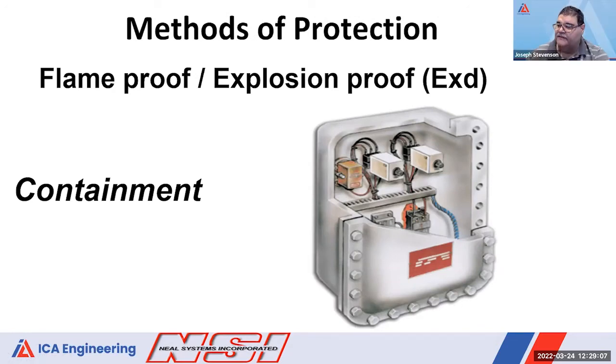Right. That's the thing, it's definitely a maintenance issue, because if you do have to access these locations, there's a lot of hoops you have to jump through, whether it be a chemical sniffer or shutting down power to the area. So a number of precautions you have to take, and people very often will cut corners, because it takes a lot of time to unbolt something with 40 bolts. So you end up with a situation that may have started out safe, but over time ends up becoming unsafe.